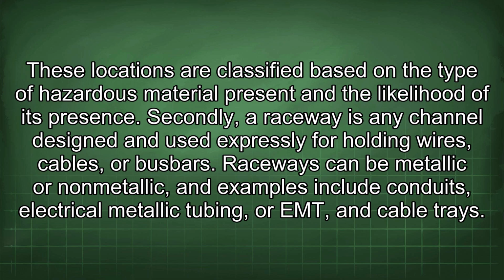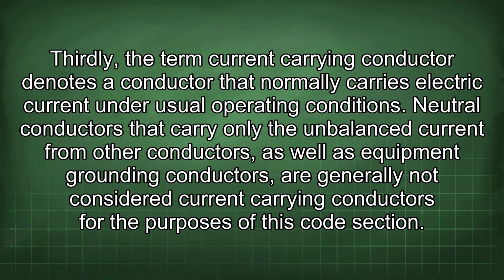Secondly, a raceway is any channel designed and used expressly for holding wires, cables, or busbars. Raceways can be metallic or non-metallic, and examples include conduits, electrical metallic tubing, or EMT, and cable trays. Thirdly, the term current carrying conductor denotes a conductor that normally carries electric current under usual operating conditions. Neutral conductors that carry only the unbalanced current from other conductors, as well as equipment grounding conductors, are generally not considered current carrying conductors for the purposes of this code section.